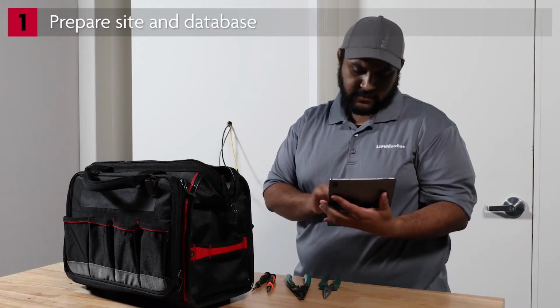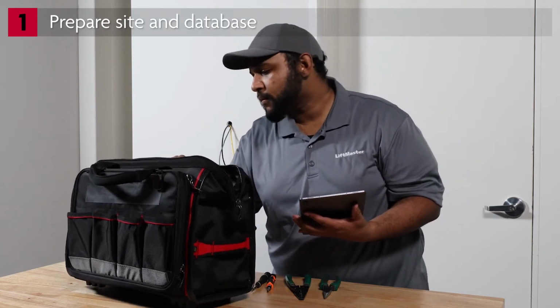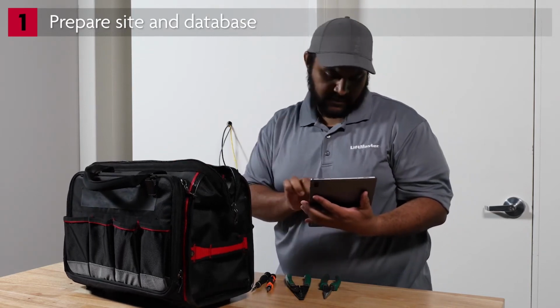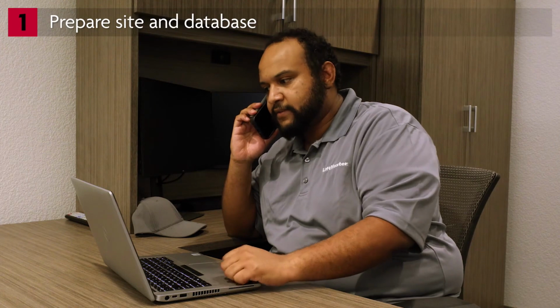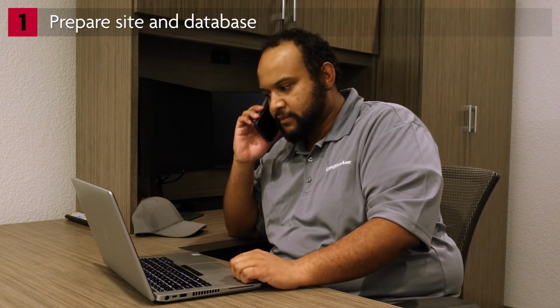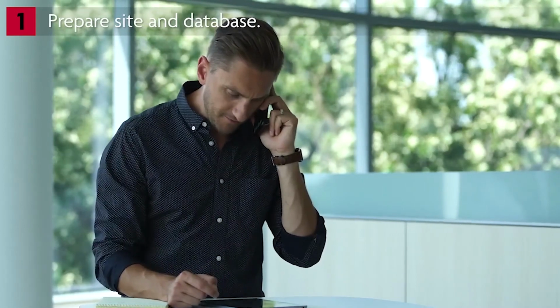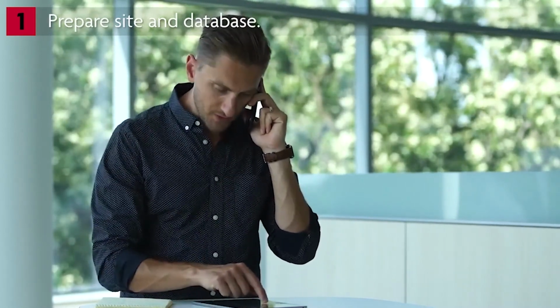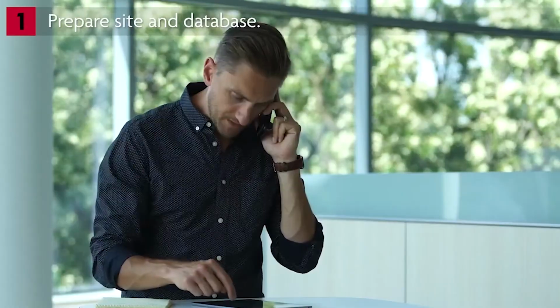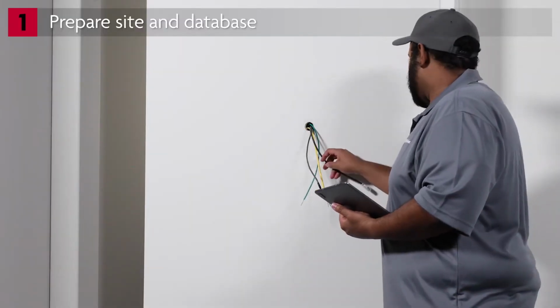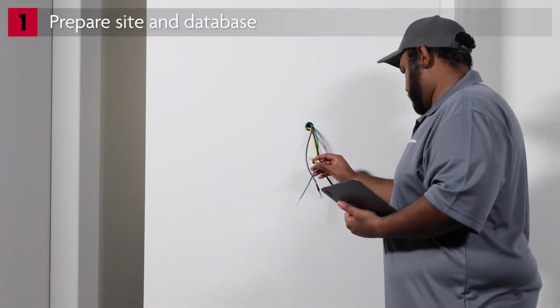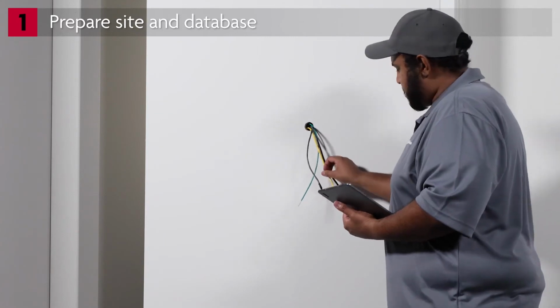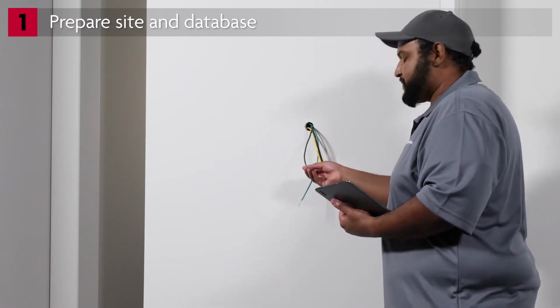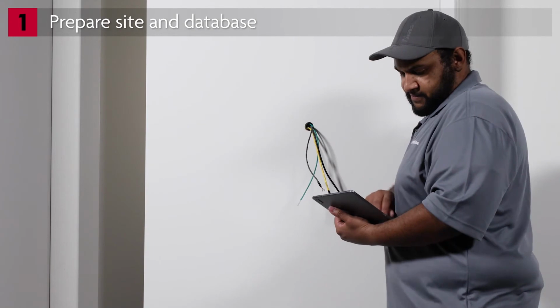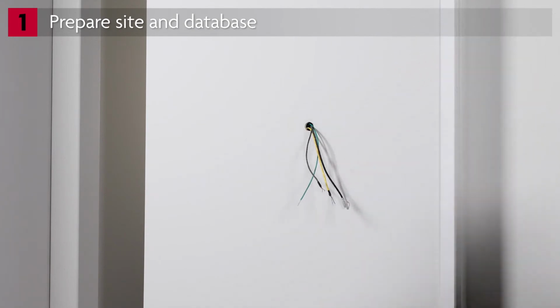Visiting the site also allows you to identify tools and other items you may need on the day of installation. In addition to the community layout, work with the community manager to obtain the contact information for all the people who will be added to the database, including residents, workers, managers, and the like. After concluding the site survey and prior to arrival for installation, work with the community manager to make sure all required wiring is routed. Power wiring and control wiring need to be routed through separate conduit.